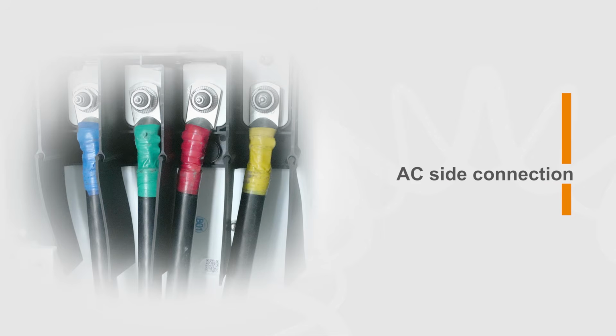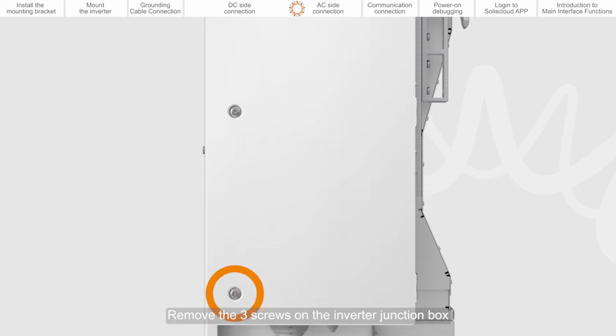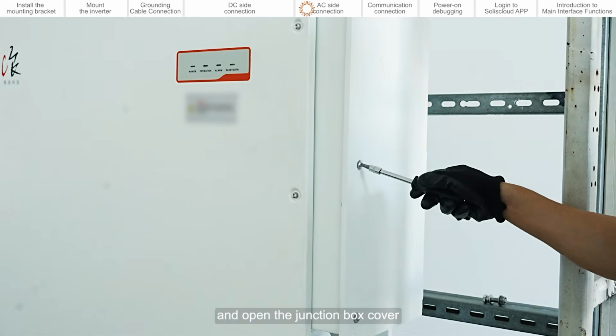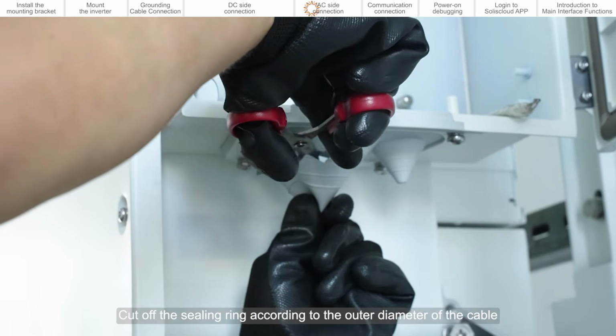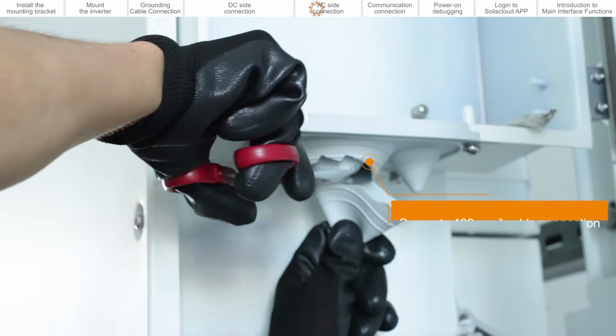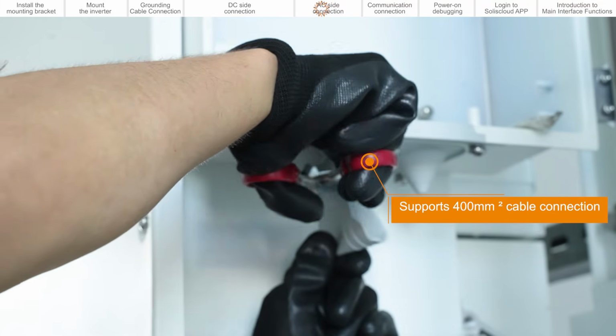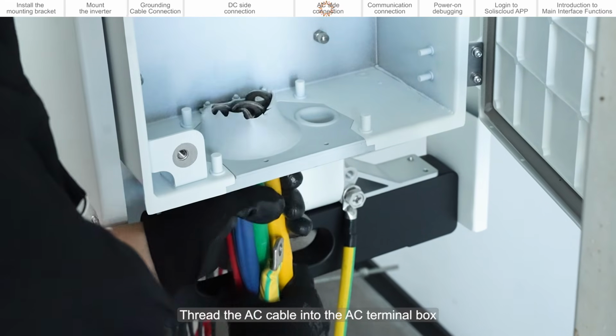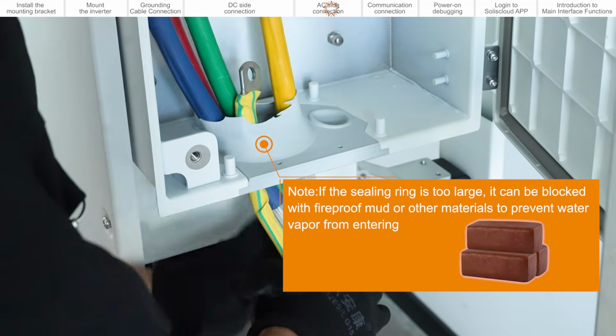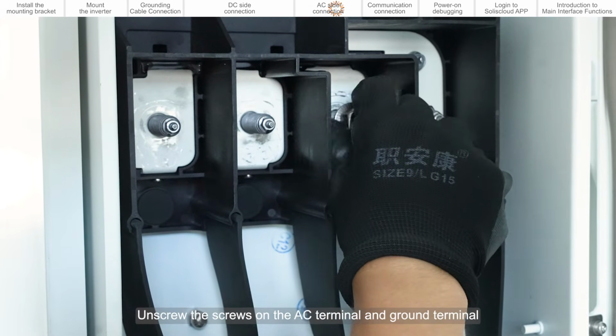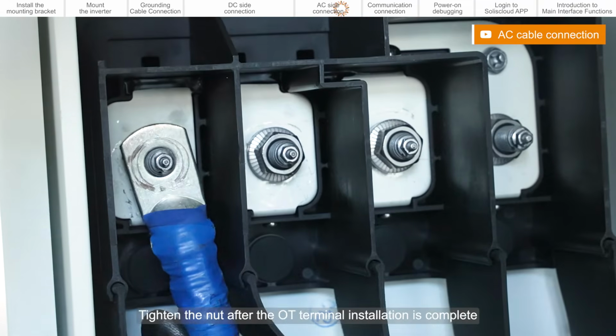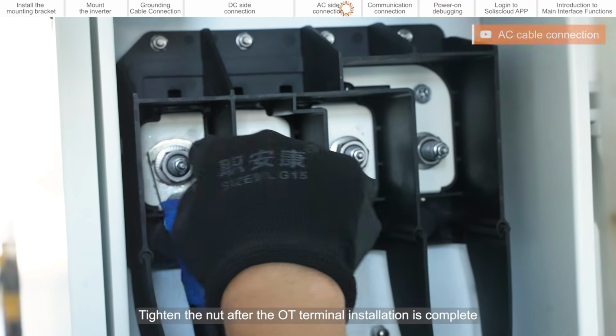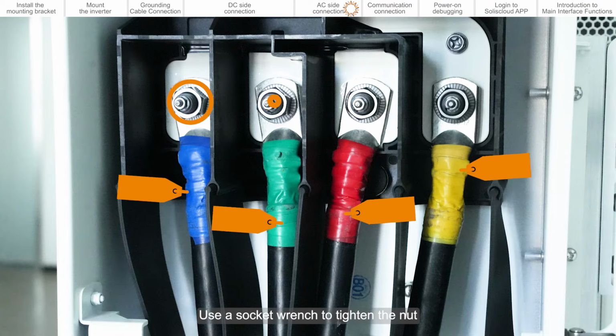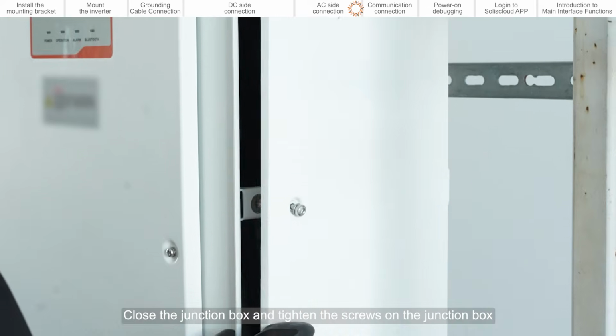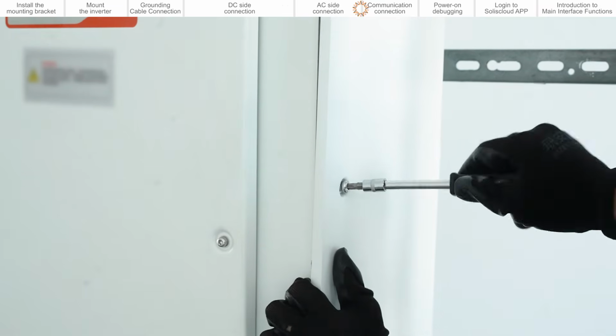AC side connection. Remove the 3 screws on the inverter junction box and open the junction box cover. Cut off the sealing ring according to the outer diameter of the cable. Thread the AC cable into the AC terminal box. Unscrew the screws on the AC terminal and ground terminal. Tighten the nut after the OT terminal installation is complete. Use a socket wrench to tighten the nut. Close the junction box and tighten the screws on the junction box.